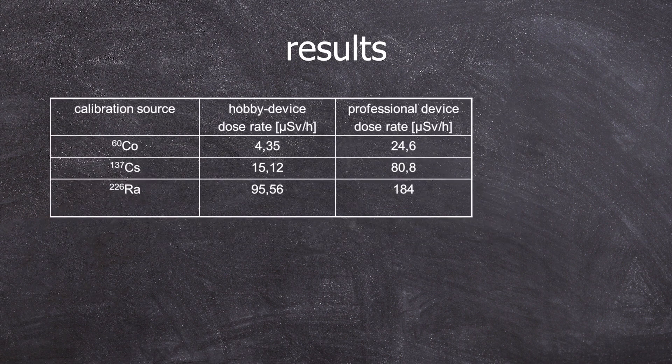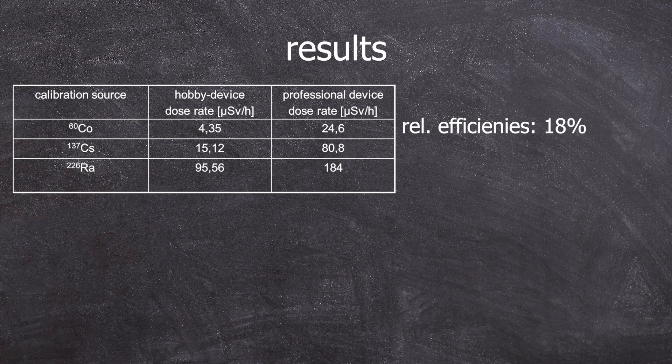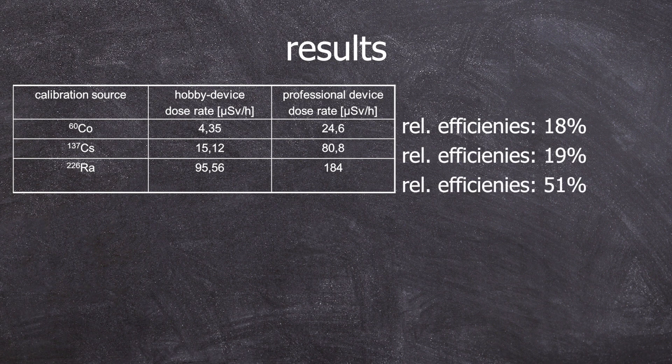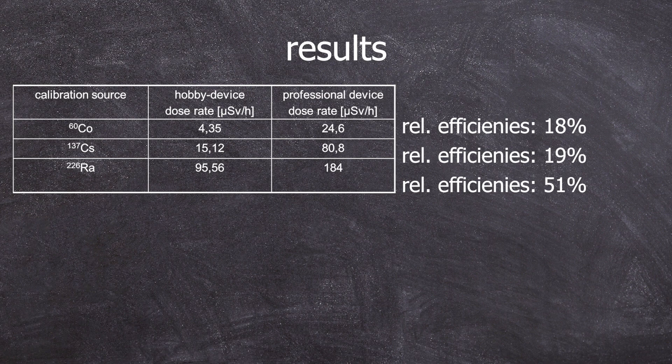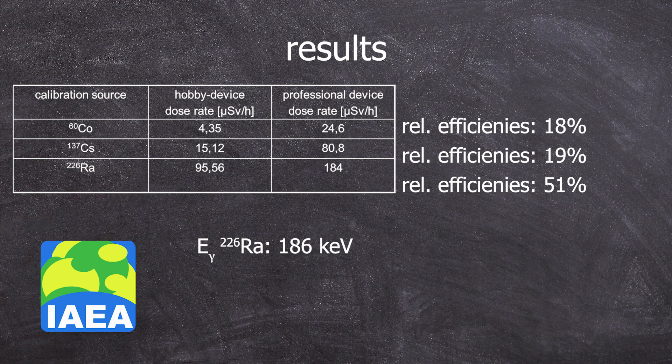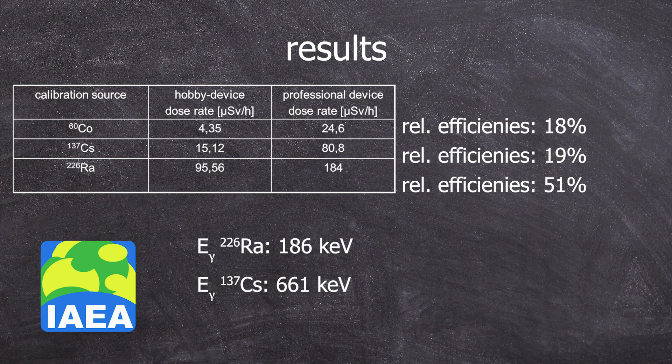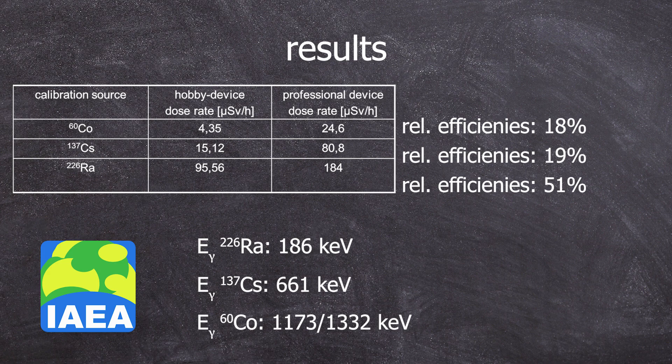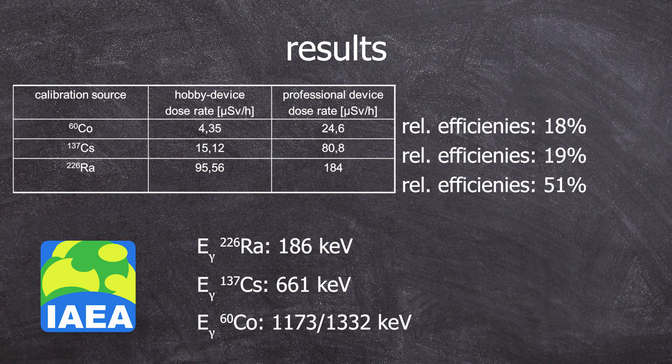Specifically, we have relative efficiencies of 18%, 19%, and 51%. I can provide you the gamma energies, but you can also find them on the Isotope browser app. Radium-226 has a 186 keV line. Cesium-137 has a 661 keV line and Cobalt-60 has one at 1173 and one at 1332 keV.